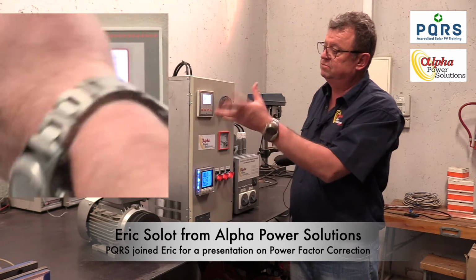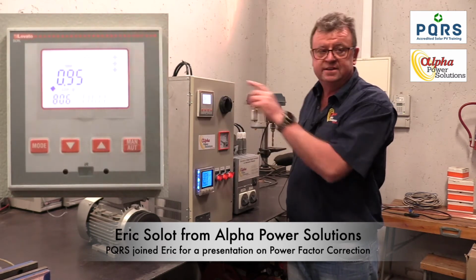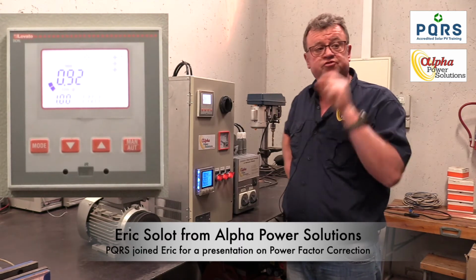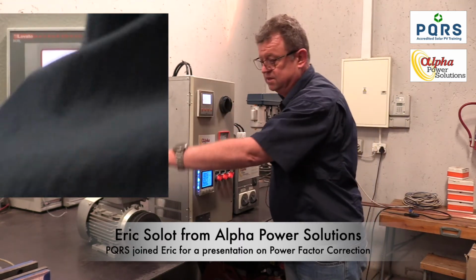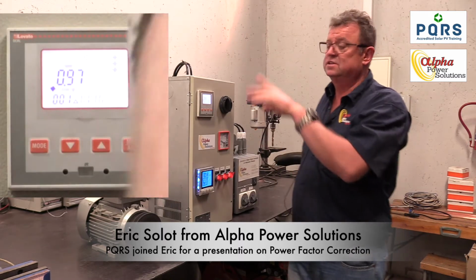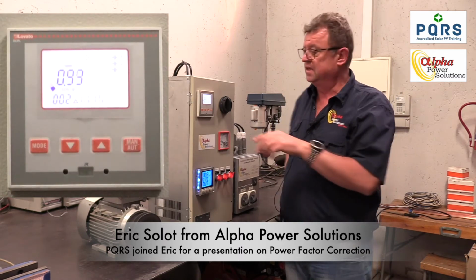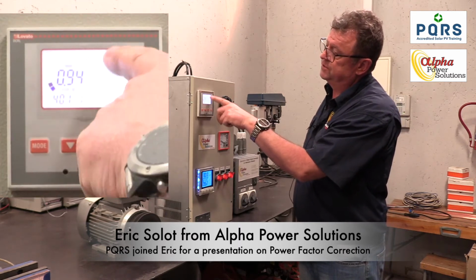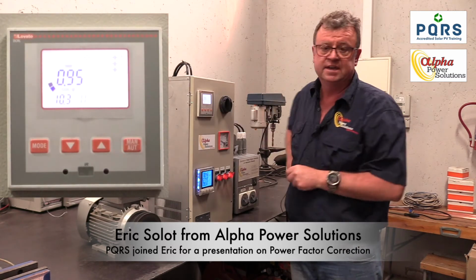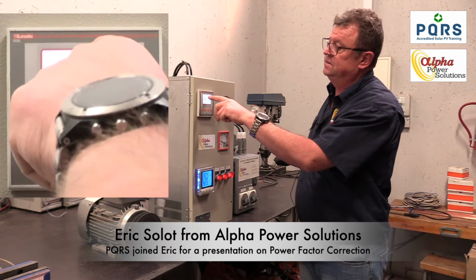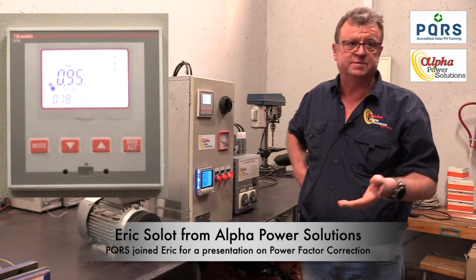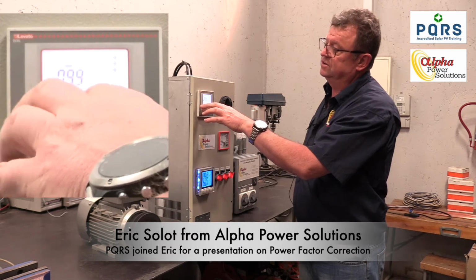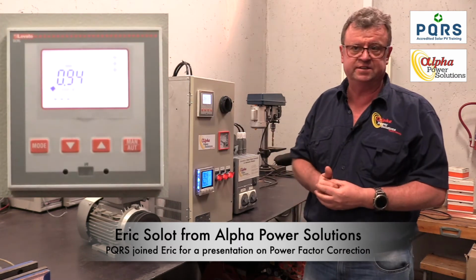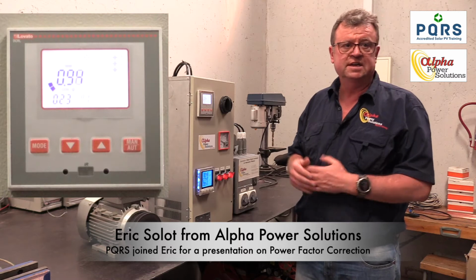Right now, the value displayed here, 0.96, 0.95, it fluctuates a little bit. That is the power factor of the load being drawn from the grid. It is not the power factor of this actual load, it is measuring the power factor of the incoming power. These are just a representation of the 3 steps, and as you can see, it's highlighted. It means that these 3 steps are engaged. This little sign here says that it is in automatic mode, and the values displayed here are all relevant factors that an electrician would want to see in case of troubleshooting.